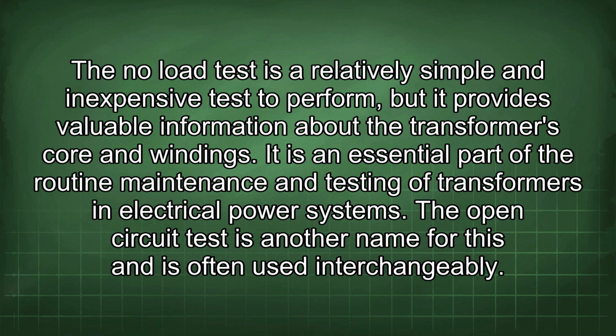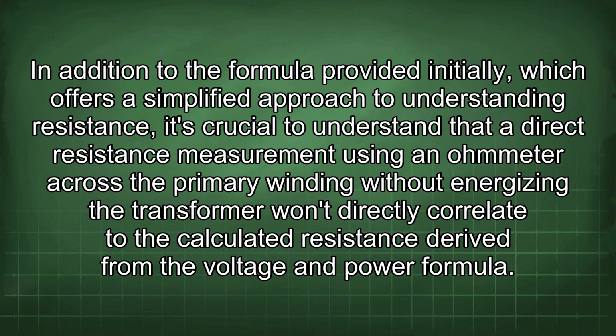It is an essential part of the routine maintenance and testing of transformers in electrical power systems. The open circuit test is another name for this and is often used interchangeably. In addition to the formula provided initially, which offers a simplified approach to understanding resistance, it's crucial to understand that a direct resistance measurement using an ohmmeter across the primary winding without energizing the transformer won't directly correlate to the calculated resistance derived from the voltage and power formula.